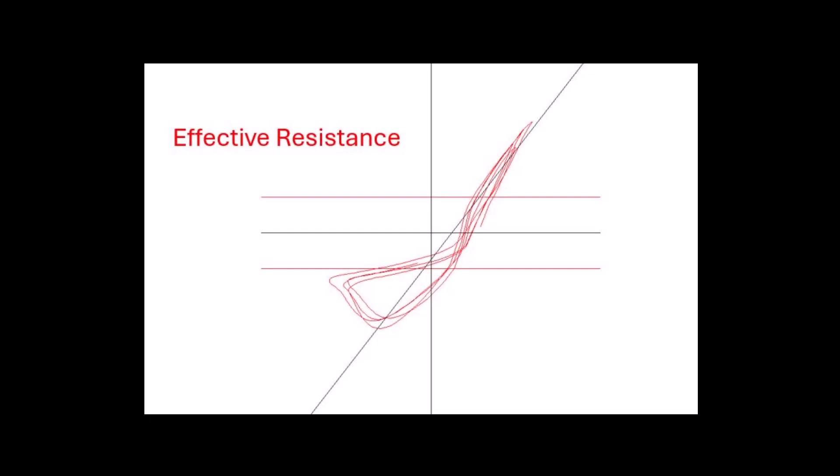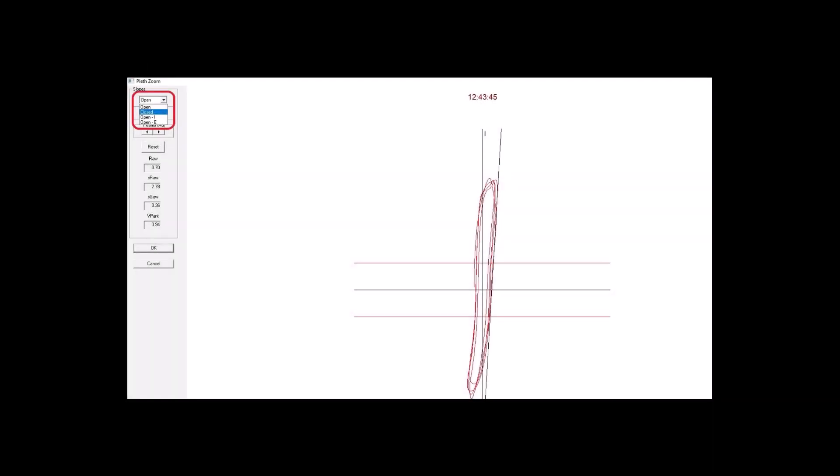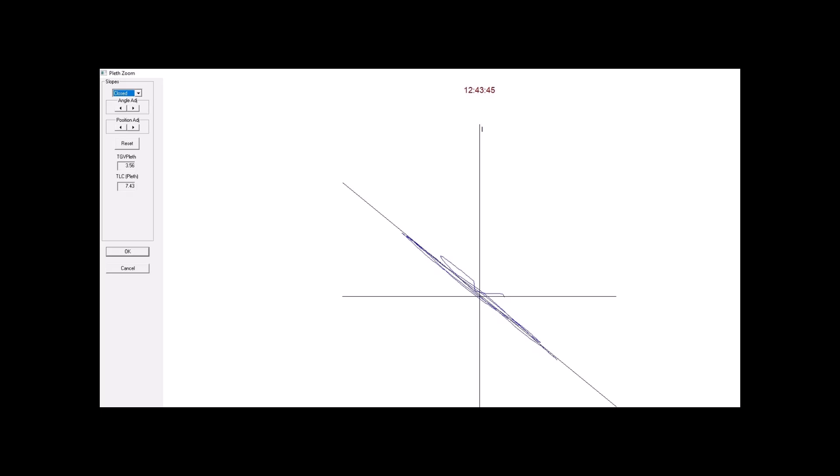The second method, described by Mattis, is also called effective resistance. This method incorporates all of the data points within the entire breathing loop and averages those points. The line of best fit shown here takes all of the data points and puts the line through the average. To adjust the line of best fit for the closed shutter breathing, select closed from the drop-down menu in the upper left. This will display the blue tracing. Adjust this line the same as the lung volume graph. When all adjustments have been made, select the OK button to return to the test screen.